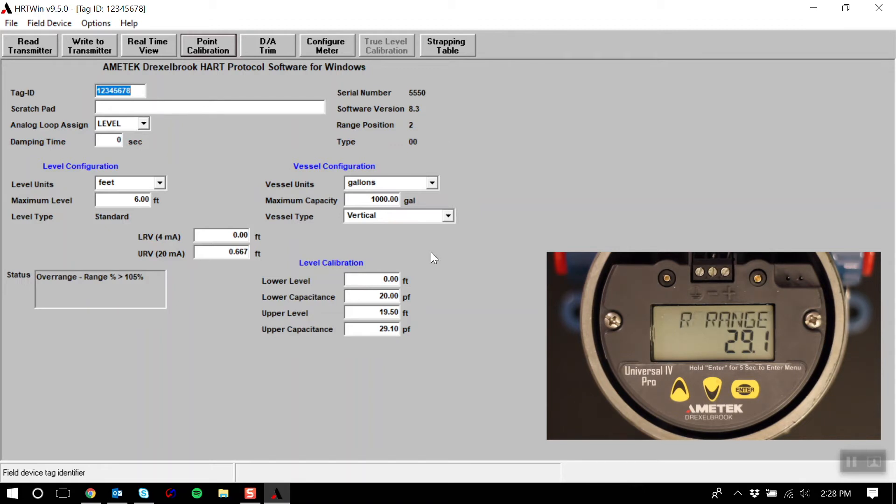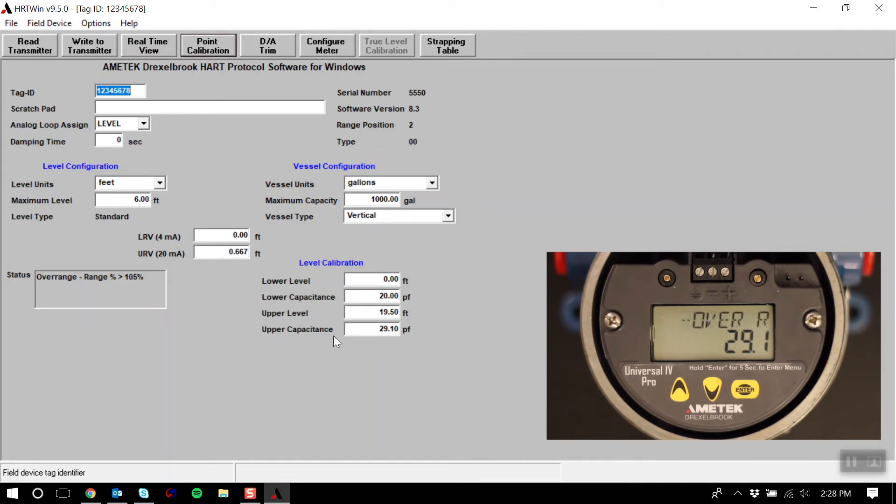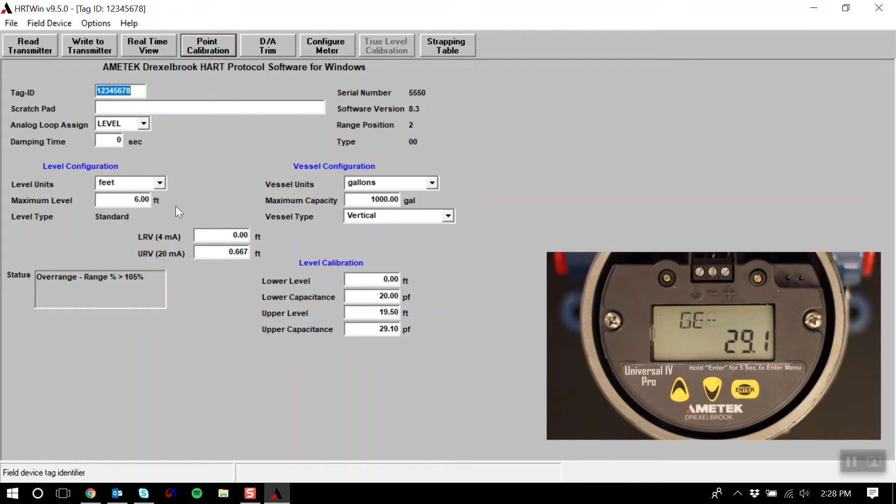To do this, you will need to know the following: the value of your lower level, the lower capacitance value, the upper level value, and the upper capacitance value. You will also need to know the maximum level your tank will see, and also your 4 and 20 milliamp control points.